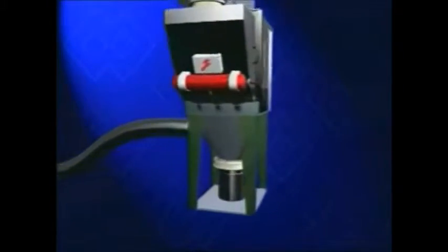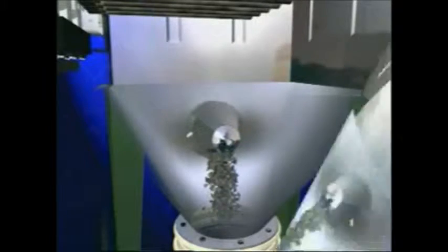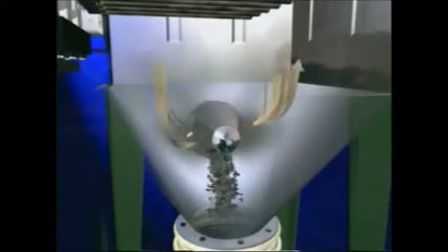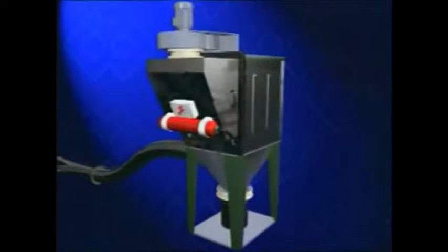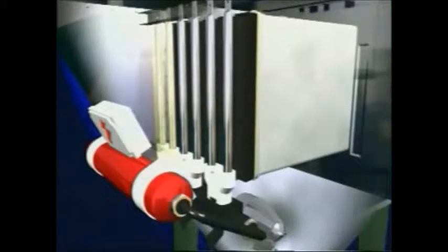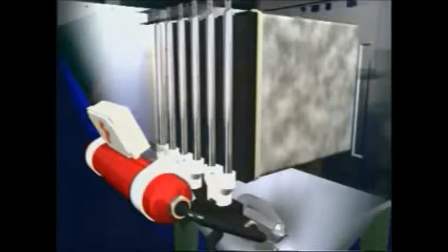The dust-laden air enters the pulse jet filter at the dirty air plenum where it expands and air velocity drops. This results in optimum air and dust distribution. Heavy particles are collected in the hopper of the dirty air plenum. The dust-laden air then passes through the filtered media, depositing the fine dust on the outside of the dust collection bags. Each bag is regularly cleaned by a reversed jet of compressed air.